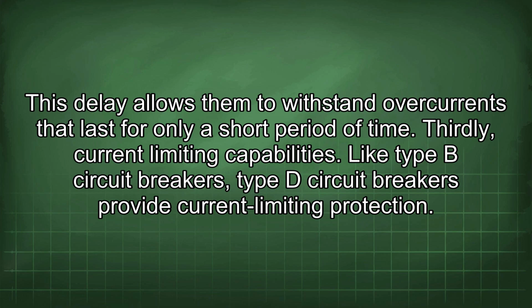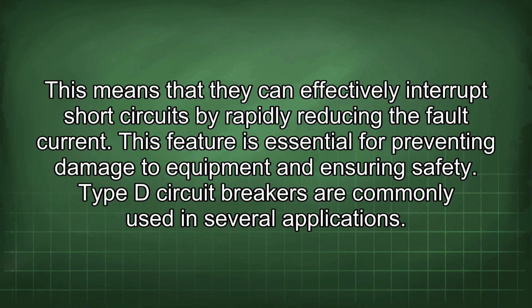Thirdly, current limiting capabilities. Like Type B circuit breakers, Type D circuit breakers provide current limiting protection. This means that they can effectively interrupt short circuits by rapidly reducing the fault current. This feature is essential for preventing damage to equipment and ensuring safety.